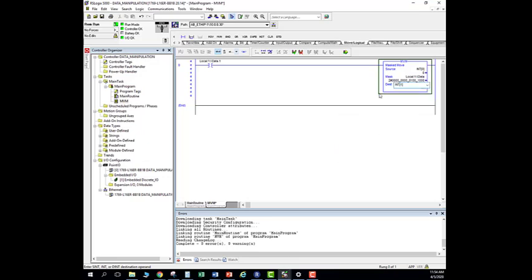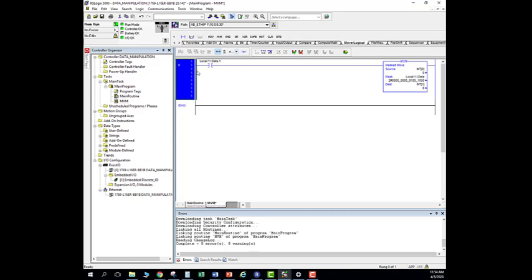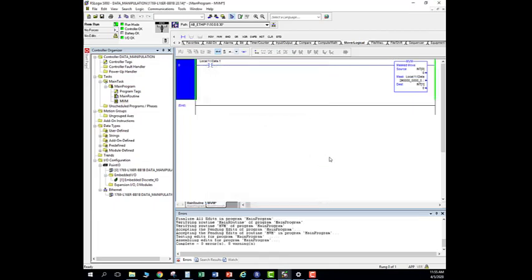Now why are we using integers? Integer is 16 bits long. How many inputs do we have associated to this processor? 16 bits. So when I'm mask moving information I've got 16 bits of my source, 16 bits of my mask, 16 bits of my destination — this is critical. We can't always move information between mismatched sizes because it gives us errors, so we've got to have the same number of bits we're manipulating in these blocks. As you can see I got some I's over here — that means I'm doing online editing — so let's finalize these edits. It seemed to like it.